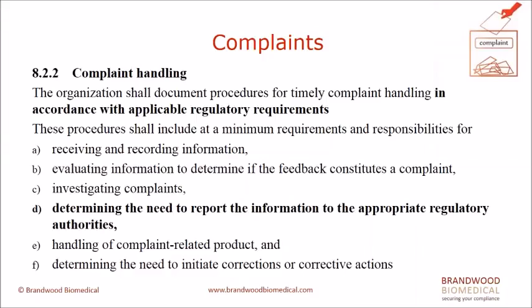The old complaints handling is still there. 8.2.2 complaint handling, so this was always there. Procedures for handling complaints, it now says in accordance with applicable regulatory requirements. So there is an explicit reference there to things like the US FDA's medical device reporting scheme and the TGA's IRIS scheme and the European vigilance and reporting arrangements, which are all effectively referenced by that clause. And you are now required to expressly determine the need to report the information to the appropriate regulatory authorities. That's always been a regulatory requirement. It's buried well there in the US CFR, for example, that it's necessary for manufacturers to review post-market complaints and actively determine whether here you've got something that's reportable and to write down your justification for what you do.